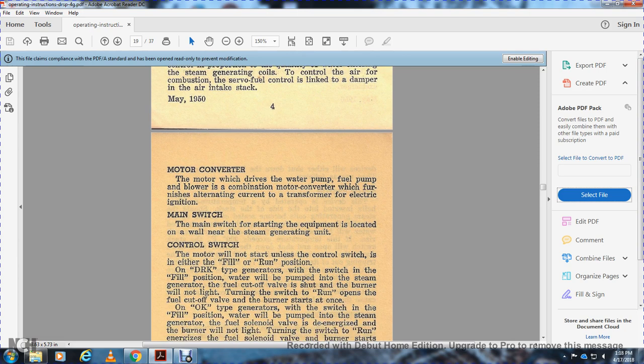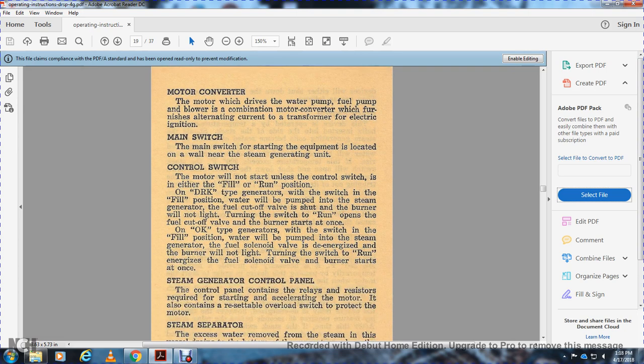The main switch. The main switch, the starting equipment, is located on the wall near the steam generator unit. Control switch: the motor will not start unless the control switch is in either the fill or the run position. On the DRK type generator, the fill position pumps water into the steam generator. The fuel cutoff valve is shut and the burner will not light with the switch in this position. In the run position, the fuel cutoff valve opens and the burner starts at once. On the OK type generator, with the switch in the fill position, water will be pumped into the steam generator. The fuel solenoid valve is de-energized and the burner will not light. In the run position, the fuel solenoid valve is energized and the burner starts at once.